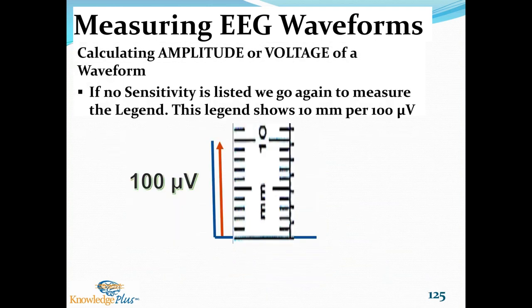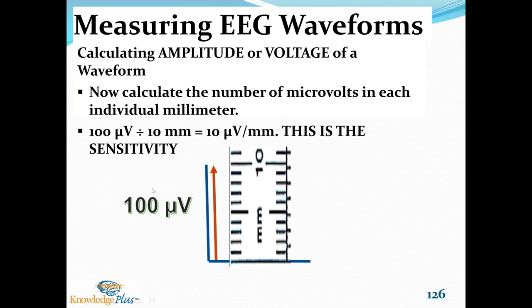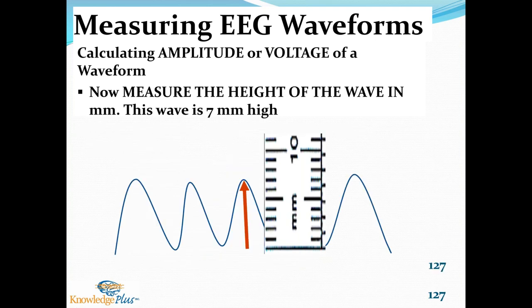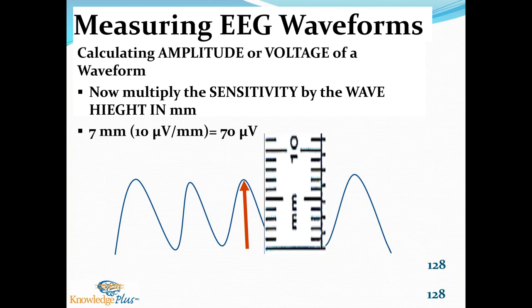If no sensitivity is listed, we go again to measure the legend. The legend shows 10 millimeters per 100 microvolts. So 100 divided by 10 means our sensitivity is 10 microvolts per millimeter. Now we can measure the height of any wave. This wave is 7 millimeters, and 7 times 10 is 70 microvolts.